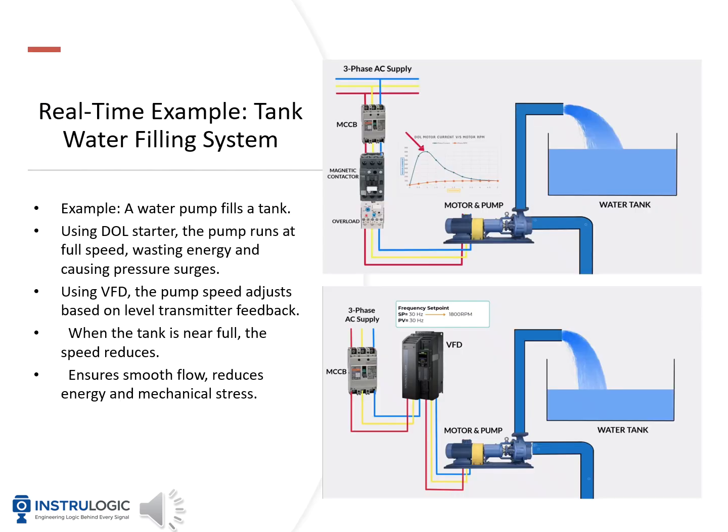Let's see a real-world example of how a VFD improves efficiency — a tank water filling system. In the first diagram, the pump is controlled by a DOL starter and runs at full speed all the time, even when the tank is almost full, wasting energy and causing pressure surges that can damage pipes and valves. In the second diagram, the pump is controlled by a VFD. The pump speed adjusts based on level transmitter feedback — when the tank is nearly full, the VFD reduces the speed, ensuring smooth flow. This saves energy, reduces mechanical stress, and prevents water hammer or pressure shocks in the system.